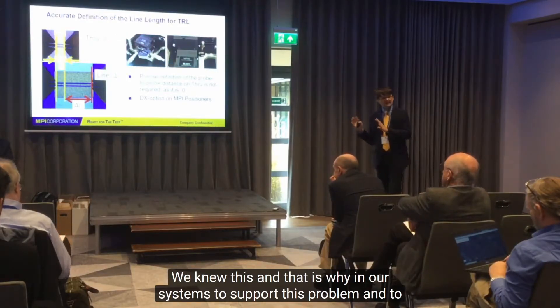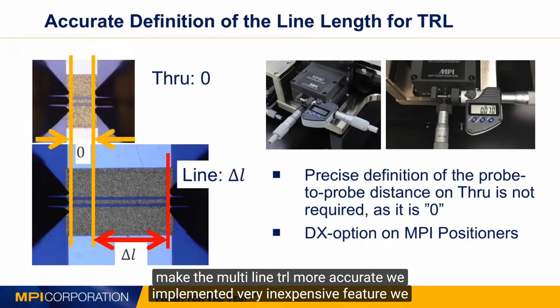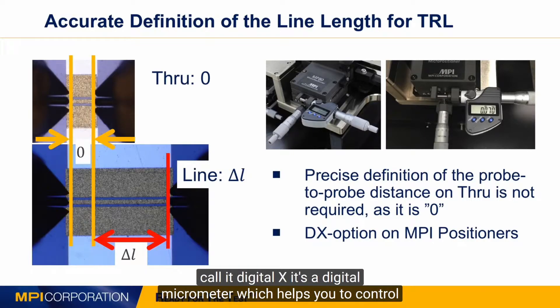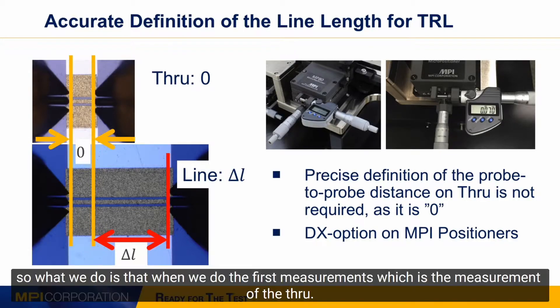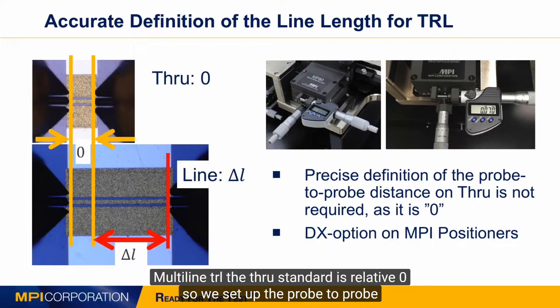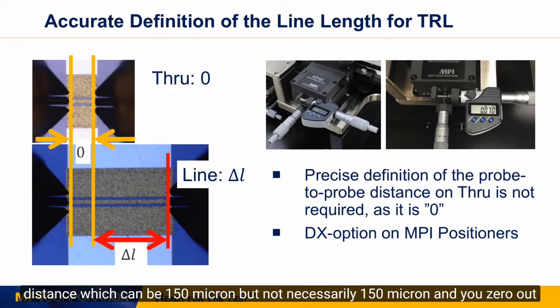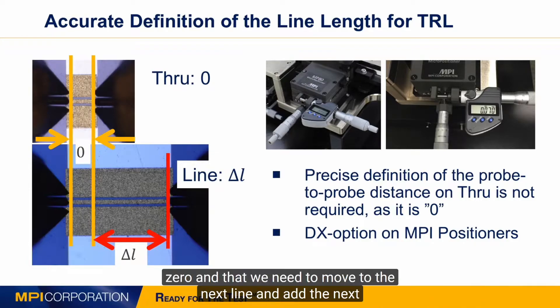Knowing this, in our systems we implemented an inexpensive feature we call Digital X — a digital micrometer that helps you control the difference in transmission line length when you do multi-line TRL on a wafer. When you do the first measurement — the through standard, which is your relative zero — you set the probe-to-probe distance, which can be 150 microns, and you zero out the digital micrometer at that position.